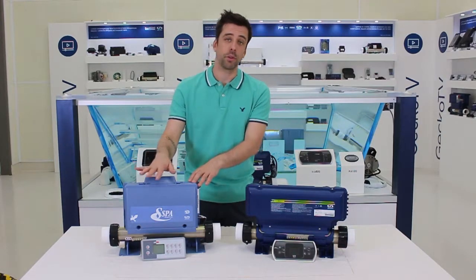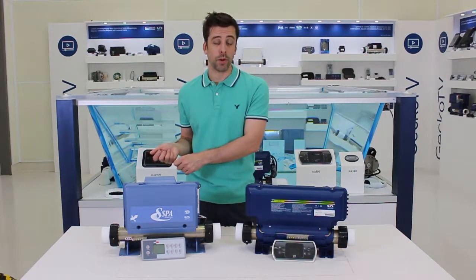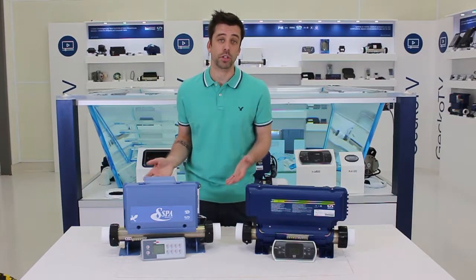It could have a board to replace. If you do have voltage at the output, however, it could be as simple as a defective accessory — a bad pump, bad blower, or such.